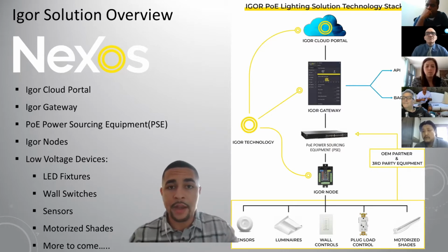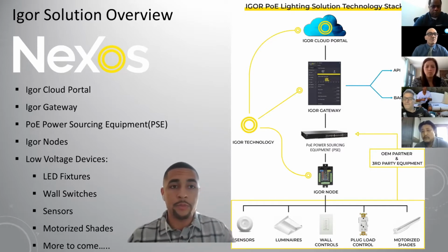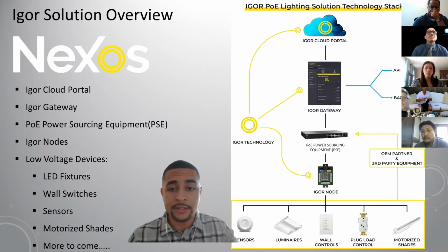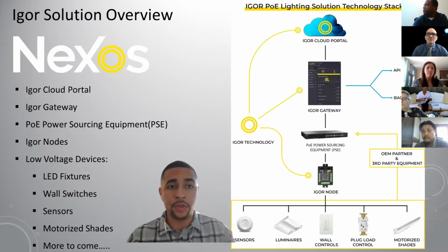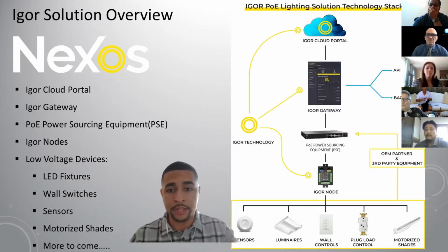From that node, it really serves two functionalities. One, it acts as the PoE driver—this is how we're able to stay agnostic, so fixtures that have a typical 0 to 10 volt driver would be removed, and now the node connects directly to the fixture board itself. It also serves as the room controller, connecting multiple devices to this node; it's not necessarily a one-for-one relationship.